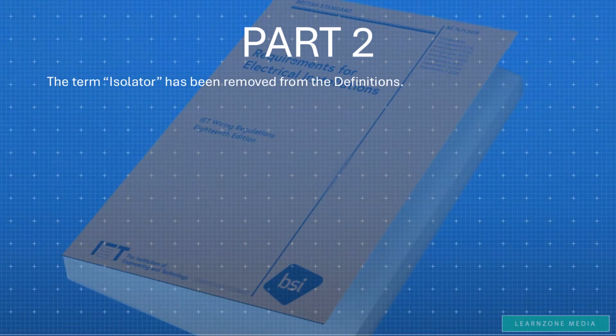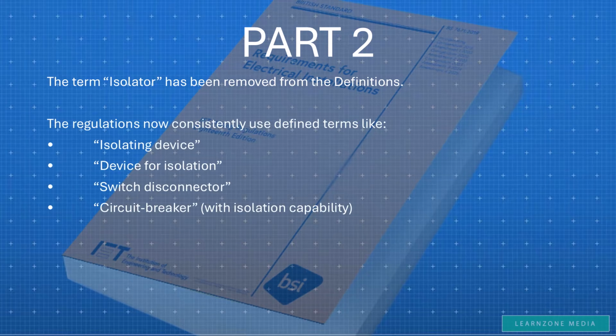Another one that I'm not so sure about is the removal of the term isolator. This is once again done to aid clarity. The regulations now consistently use defined terms like isolating device, device for isolation, switch disconnector, circuit breaker with isolation capability.